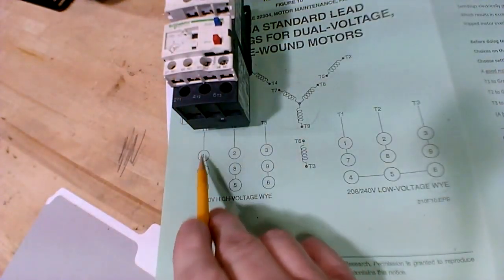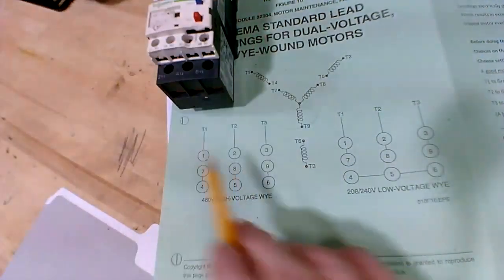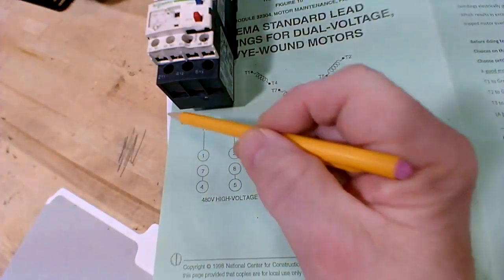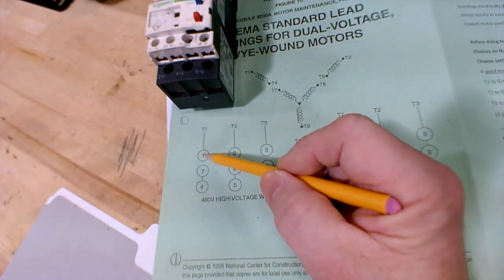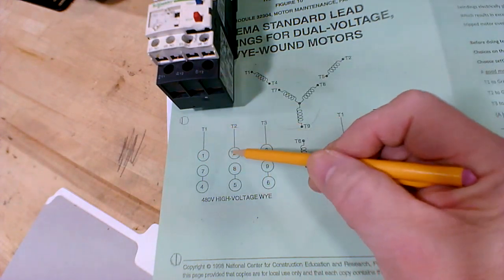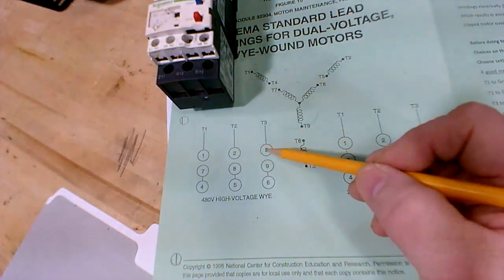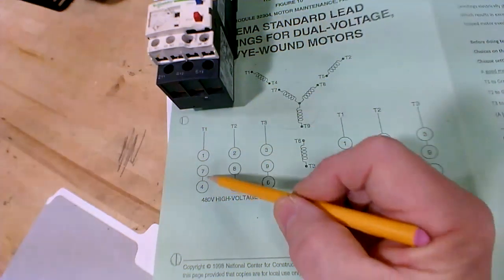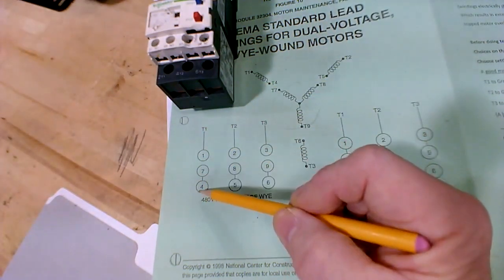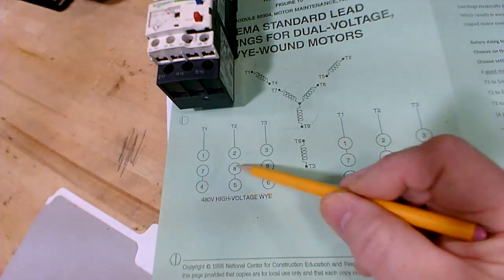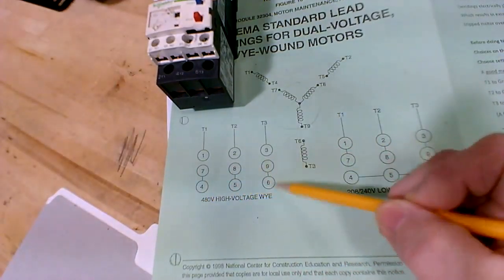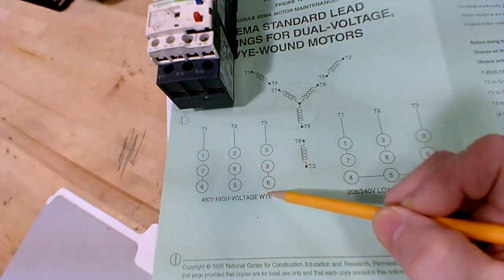T1 from the starter, it runs to just 1 only. So wire number 1 in the motor, you run from T1 just to 1 only, and you wire another. The T2 goes to 2 only. T3 goes to 3 only. And then you put a wire nut around 4 and 7. You put another wire nut around 5 and 8. You put another wire nut around 6 and 9.